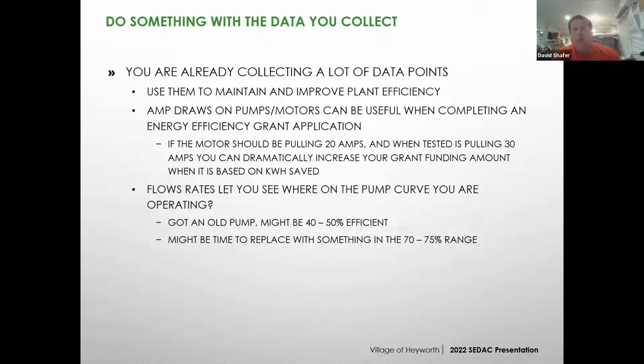Beyond that, if you're operating with old pumps, look at where you're at on the pump curve. What's that pump efficiency going to be? You might be operating in the 40 to 50% efficiency range. It might be time to replace those pumps and push yourself up into the 70, 75% range, if that's a possibility.